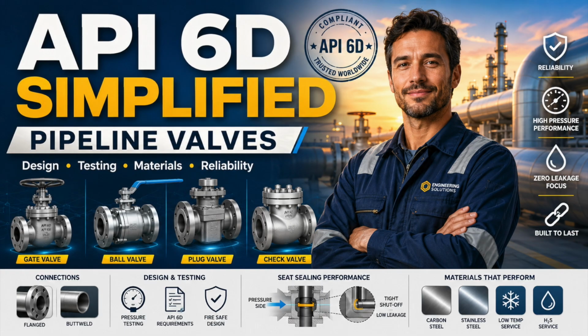Two valves with the same size and pressure class may behave completely differently. One may seal in both directions. Another may seal in only one. One may self-relieve cavity pressure. Another may trap it. One may pass an intelligent pig. Another may contain a step, seat intrusion, or reduced internal geometry that creates obstruction. One may provide tight shutoff with soft seats. Another may use metal seats and allow controlled leakage. So the real engineering principle is simple. Do not select the valve before you define the function.